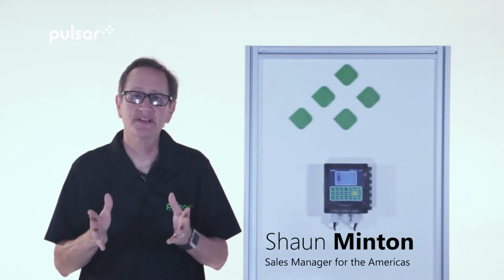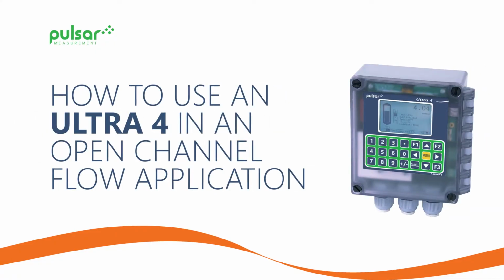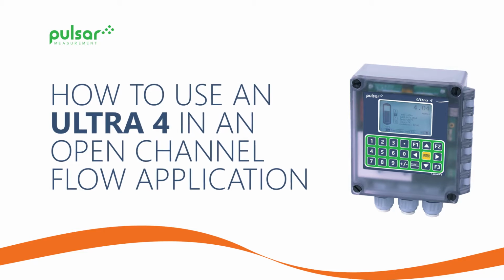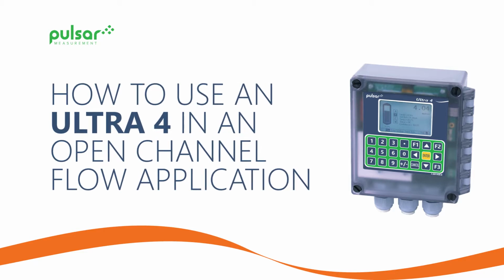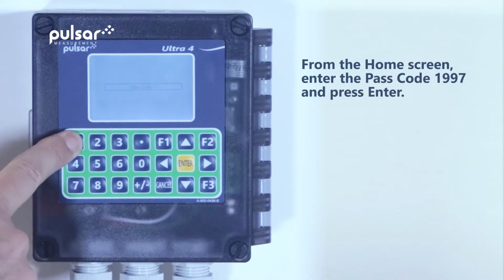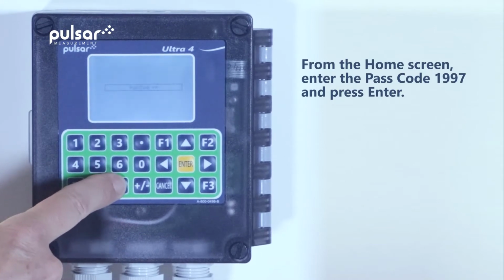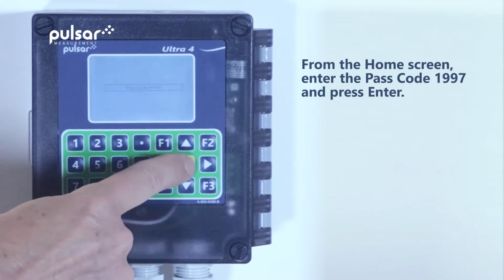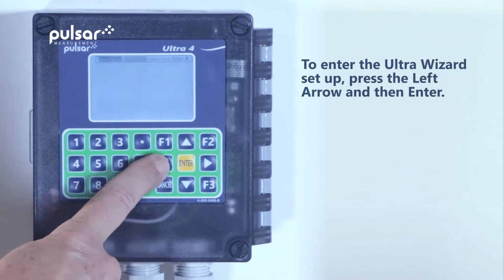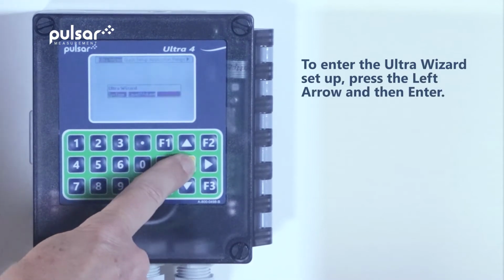My name is Shaun Minton, and in today's how-to video, we're going to teach you how to use the Ultra 4 controller in an open channel flow application. From the home screen, first we'll enter the passcode 1997 and then press enter. Next, we'll get into the Ultra Wizard setup by hitting the left arrow key and enter.